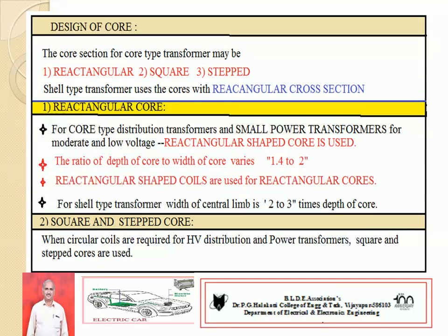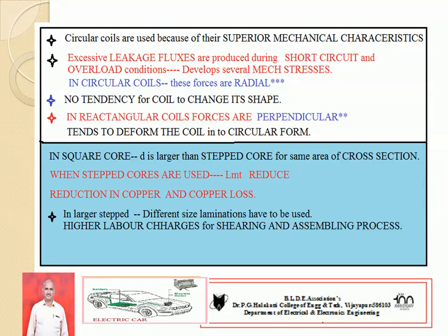Square or stepped type cores are used when circular coils are required in power transformers and distribution transformers. It is possible to use either circular coils or rectangular coils. Rectangular coils are used and circular coils are also used — so what is the difference? If you are using circular coils, these coils are superior in mechanical characteristics because when the transformer is subjected to short circuit or overload conditions, leakage fluxes produce a huge amount of mechanical stresses.